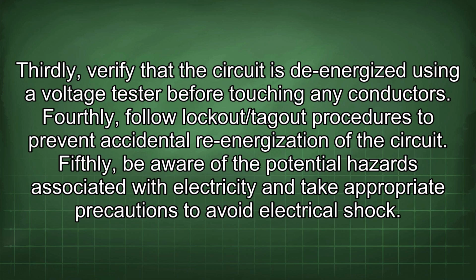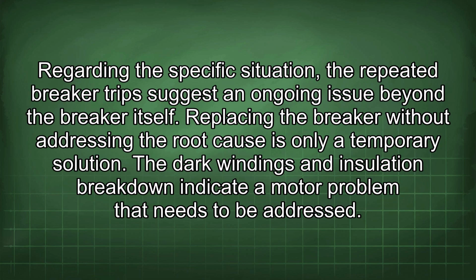Fifthly, be aware of the potential hazards associated with electricity and take appropriate precautions to avoid electrical shock. Regarding the specific situation, the repeated breaker trips suggest an ongoing issue beyond the breaker itself. Replacing the breaker without addressing the root cause is only a temporary solution. The dark windings and insulation breakdown indicate a motor problem that needs to be addressed.